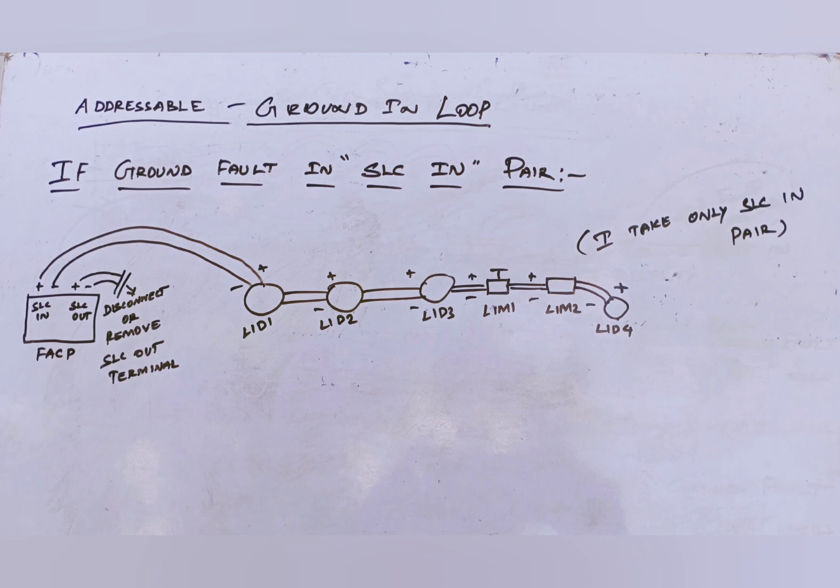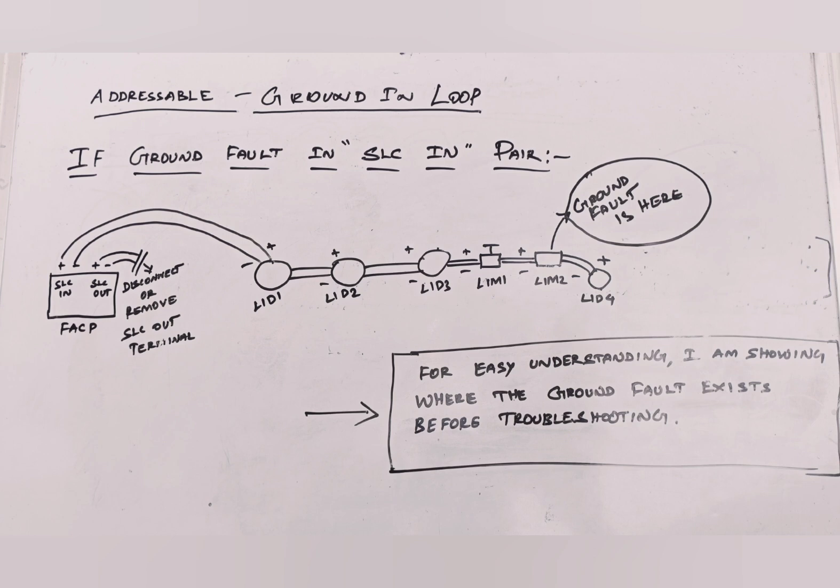First of all, I am taking SLC in pair wire devices. To find out the ground fault easier. This is the best way. So I can disconnect the SLC out pair wire. So we don't have any interrupt over there. For your understanding, I am showing the place where we have ground fault as shown in figure.